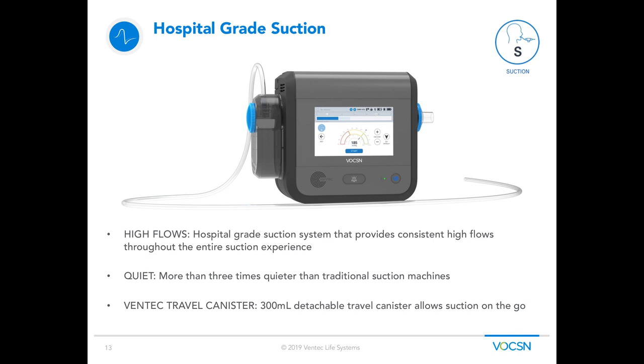So you see in this image, we have a travel suction canister on the side that can pop on or off, that can be rinsed and reused, or it can be single-use and disposed of. That suction canister gives you the ability to flip on suction with VOCSN and have hospital-grade suction with you at all times, maintaining consistent high flows. As you press and hold at the end of the tubing, you can see it's not ebbing and flowing. It's set to whatever vacuum pressure you have it set to.